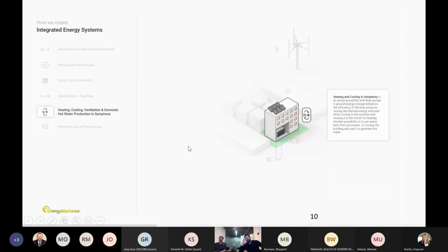We combine the heating, cooling, and ventilation in symphony. This allows for the capture of waste heat instead of exhausting it out of a building, as is the traditional method of cooling a building. We actually take that waste heat, reroute it back in through the air handling units. Via indirect evaporative cooling, we can lower the temperature, but you can also guarantee zero cross contamination, which is quite important for these COVID times.